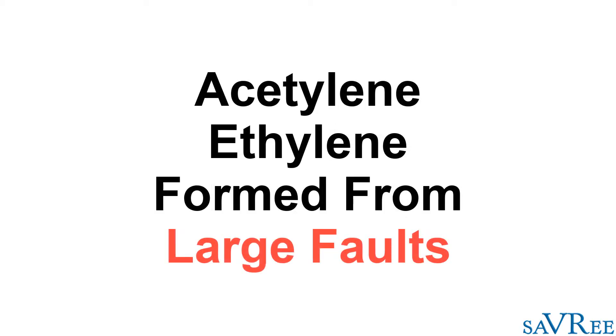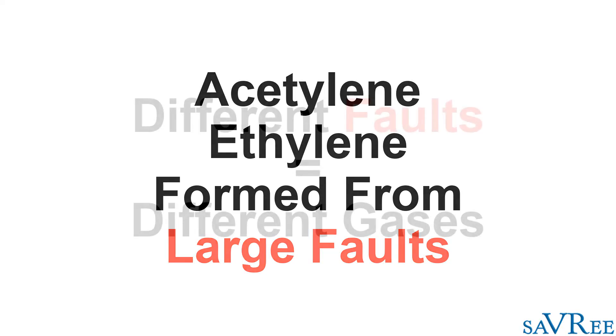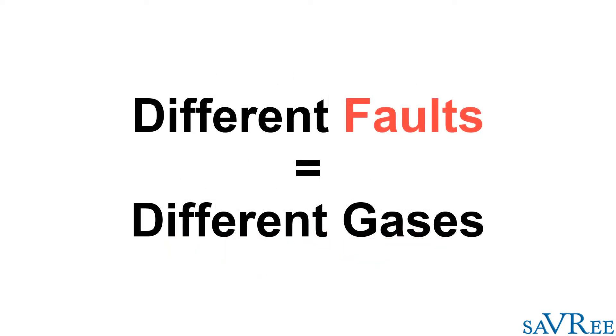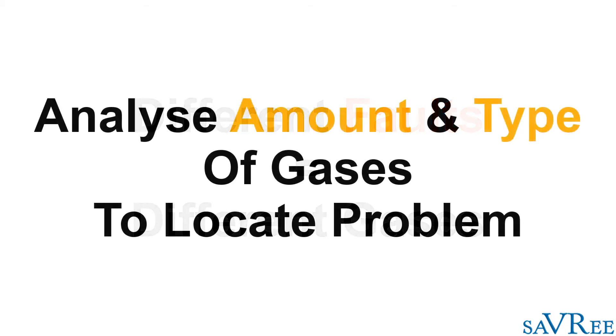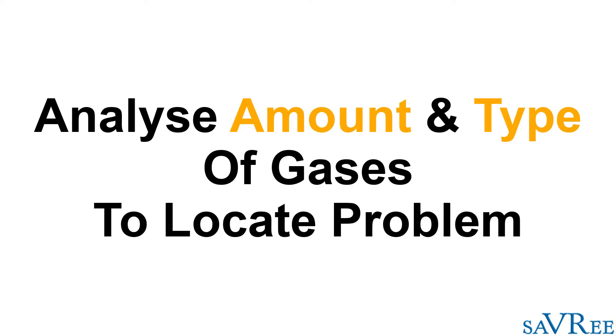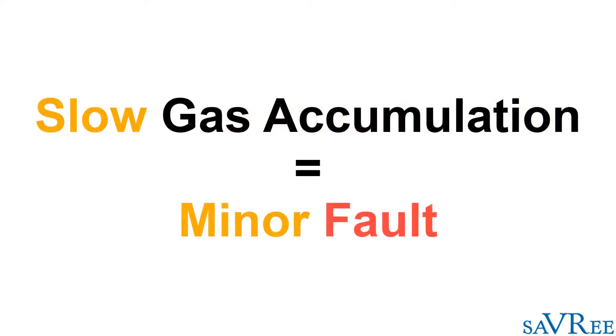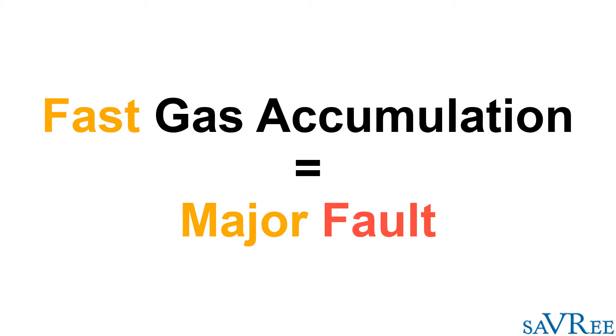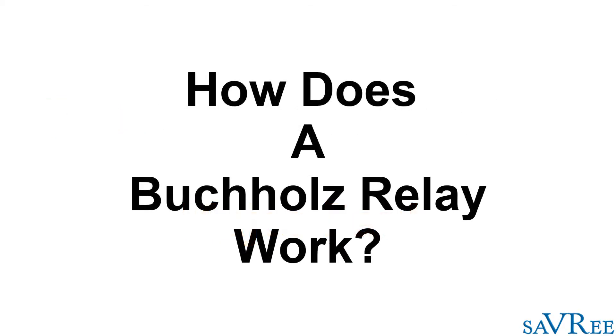When you have lesser faults or faults with not such a large amount of energy, then you will produce different gases. But the key point to remember here is that any fault, small or large or medium, is going to create some sort of gas. The amount of gas is very interesting and worth analyzing. You may get a slow trickle of gas coming out of the transformer, which means you have a low partial discharge maybe within the transformer itself. However, you may also get a very large fault, and this sudden fault creates a lot of gas very quickly.